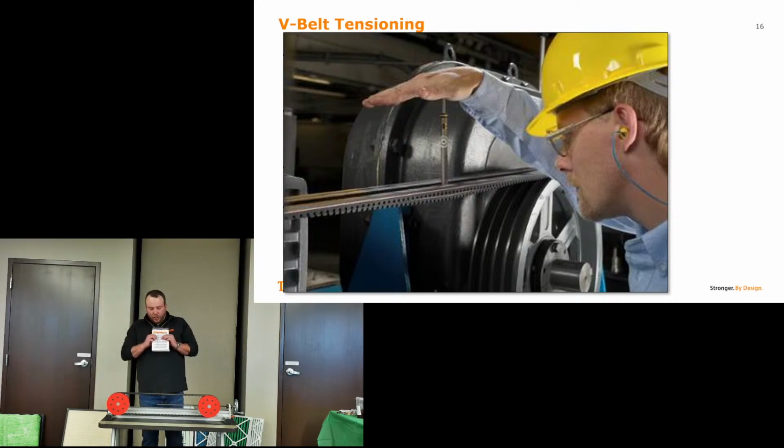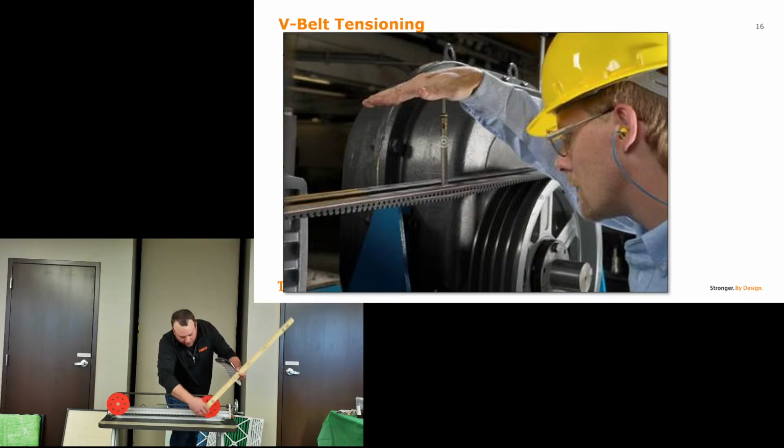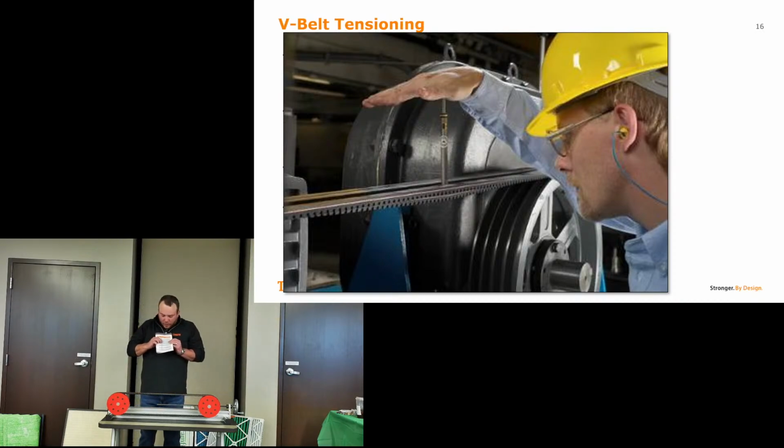And then we are going to just pick an RPM for our motor, right? Most motors are about 1800 RPM. So we'll go with the 1800. And then I'm going to take a diameter of my smallest sheave. I know from experience these are 6-inch sheaves. So I will use the 6.0 row here. So BX 1800 6.0, and then I'll pick the last column based on the ratio of my smallest sheave to my largest sheave. So right here in this system, they're both 6-inch sheaves. I'll pick the first column, and I'm looking for a deflection force of 6.0 pounds.